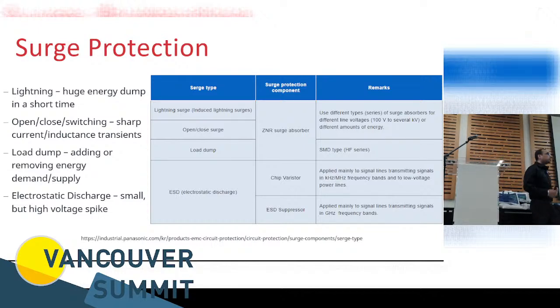So on microinverter devices, obviously we put them on the AC side. With string inverters, sometimes DC side, sometimes it depends. Ideally, it actually depends, so there is a way to predict, well, I won't say predict exactly. There are studies that map the number of lightning strikes you get per square mile or per square kilometer per year.